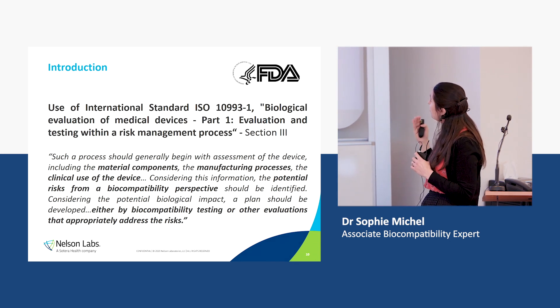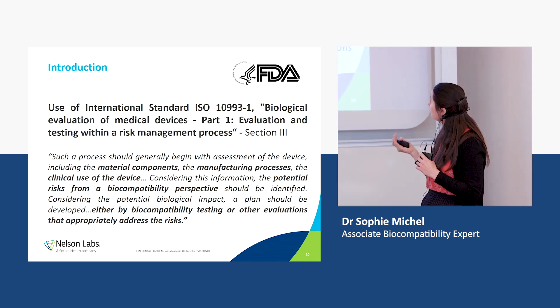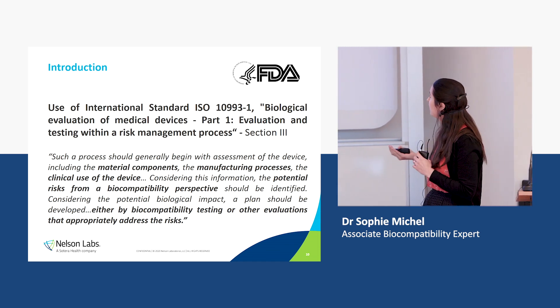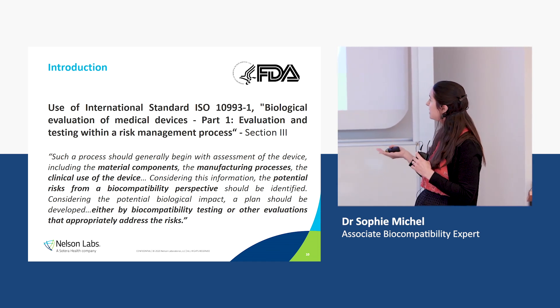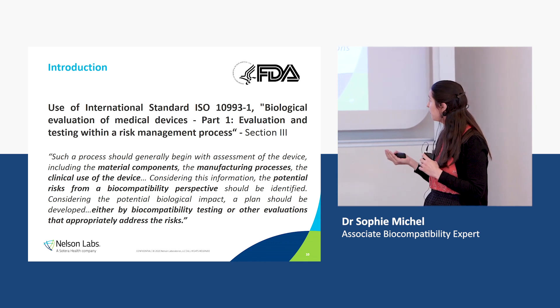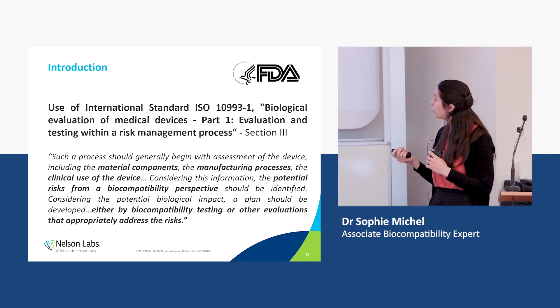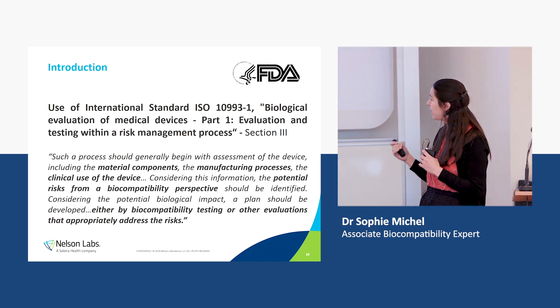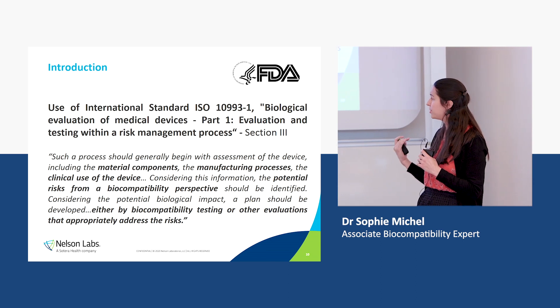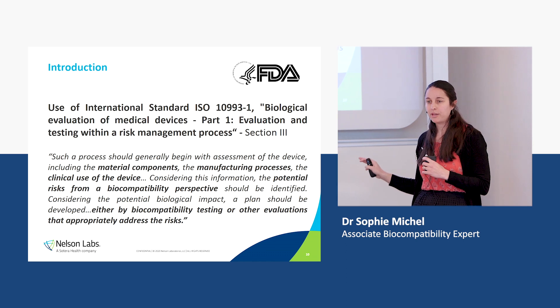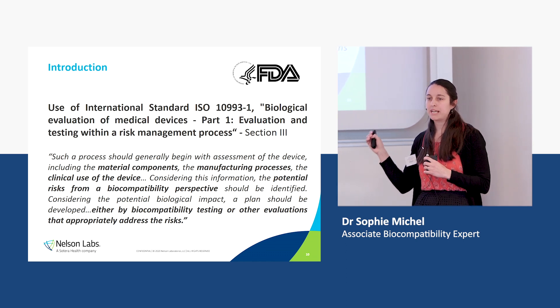The same is actually written in the FDA guidance on ISO 10993-1. A process of biological evaluation plan generally begins with assessment of the device, including the material components, the manufacturing processes, the clinical use of the device. Considering this information, the potential risk from a biocompatibility perspective should be identified. A plan should be developed — either by biocompatibility testing or other evaluation — that appropriately addresses the risk. So that is the theory, but now how we will do it in practice.